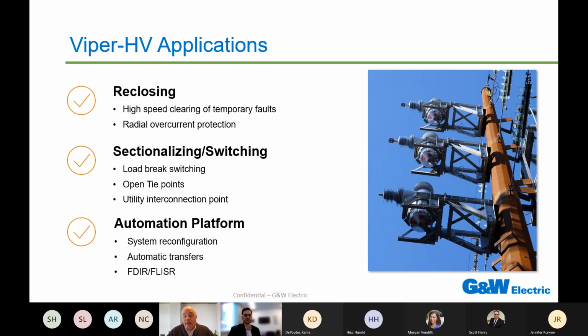Sectionalizing and switching: the legacy products available within substations or outside on the main lines are really legacy motor-operated disconnect switches, very simple devices that basically allow isolation, could be manual or automated, but have no ability to isolate current or faults. So the ability to provide this product as a retrofit solution, replacing air disconnect switches that are heavy in maintenance, allows load break switching, opening tie points within the grid, and interconnection points with our utility customers.